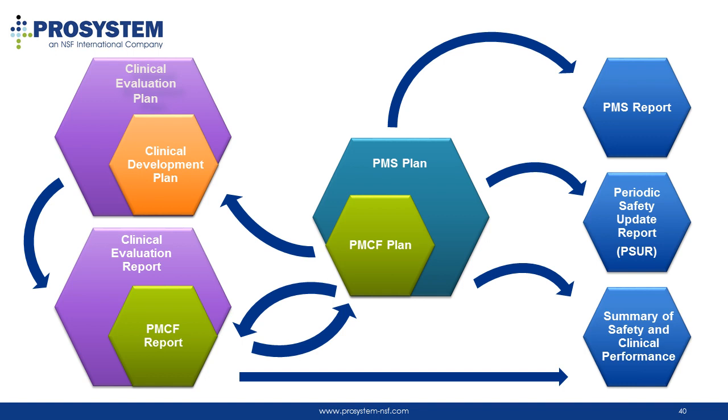Finally, PMS and PMCF activities should also be considered in the PMS reports, in the periodic safety update reports, and in the summary of the safety and clinical performance. The summary of safety and clinical performance should also include a summary of the clinical evaluation.